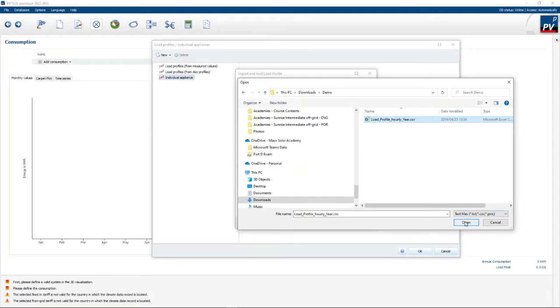Probably the best way is to add a load profile from measured values. Here you can actually import a load profile from a logger that you've installed over a period of time. In this case I'm going to import a load profile — I've got hourly values, so my interval is 60 minutes over 365 days. My unit is kilowatt, and once I confirm the format the data is imported and I've got my load profile into the system.